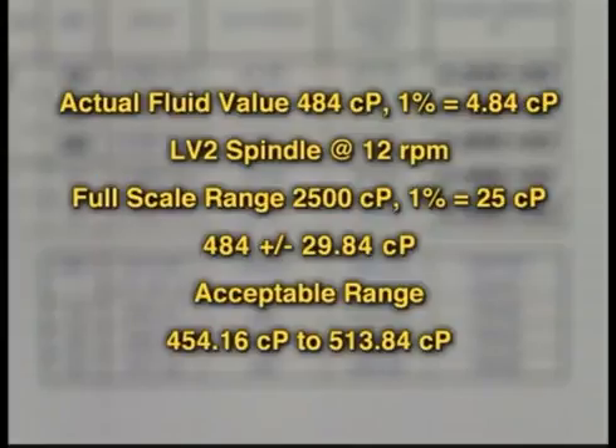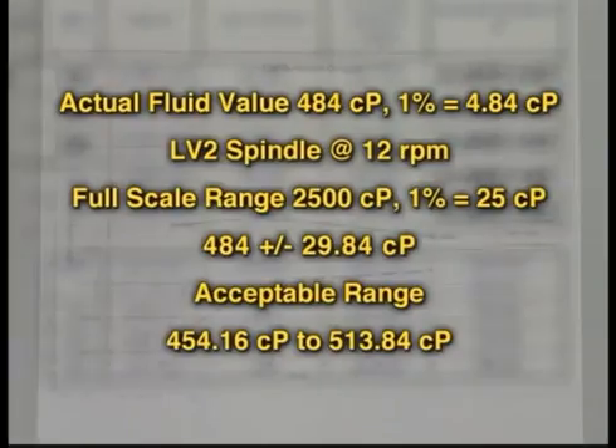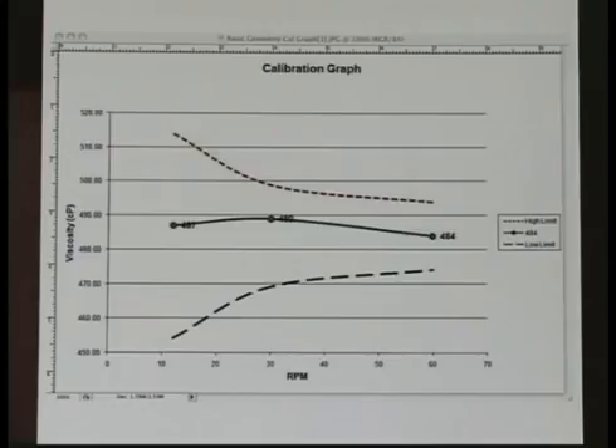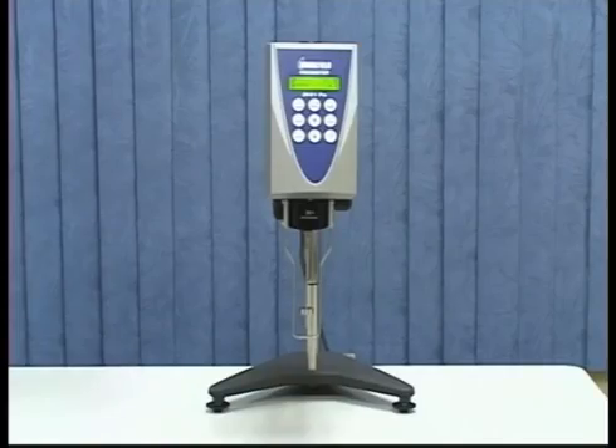Simply put, the actual fluid value is 484 centipoise, and 1% of this value is 4.84 centipoise. At a speed of 12 RPM, the full-scale range is 2500 centipoise, and 1% of this value is 25 centipoise. Thus, the tolerance on the fluid at this speed with this LV2 spindle would be 484 plus or minus 29.84 centipoise. You can see a graph of your results with this worksheet and the tolerances. Select the Calibration Graph tab to view the results. The data points are plotted and upper and lower tolerances shown. In this example, you can see the data points came within tolerance. And that's it. You have performed a calibration check.